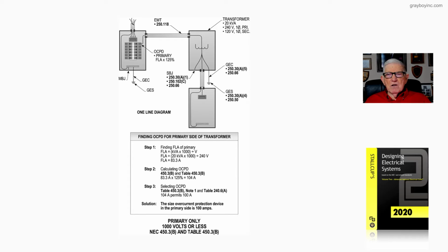Then on the secondary, we're making a 10-foot or 25-foot tap, say. And we're wanting to size that overcurrent protection device in the primary side where the transformer is rated, as you see in the illustration, 20 kVA, 240 volt primary, and a 120 volt secondary. And then, of course, you have the EMT being used as an equipment ground from the panelboard to the transformer in accordance with 250.118.